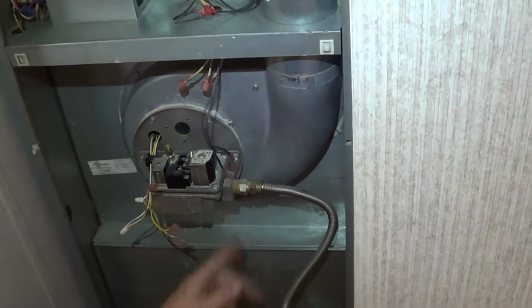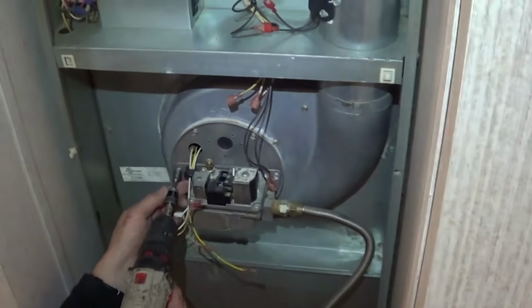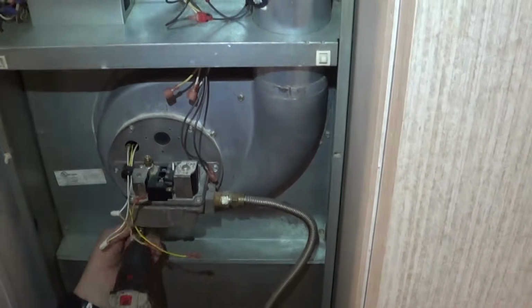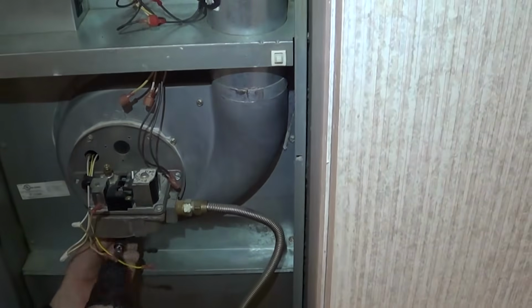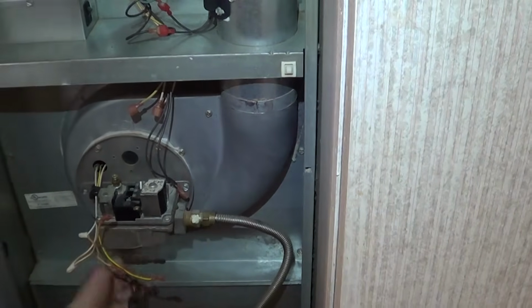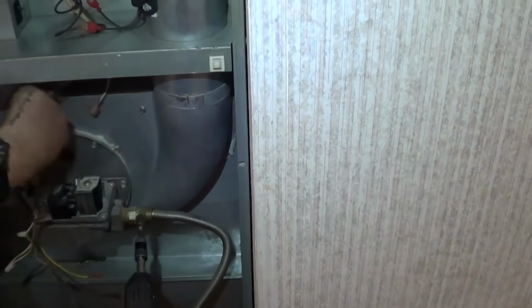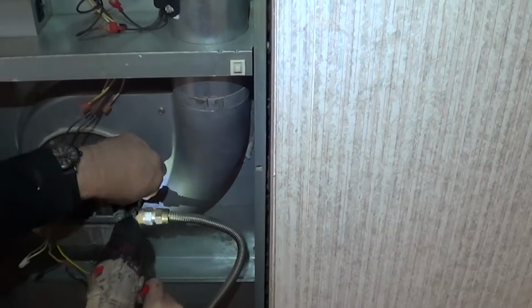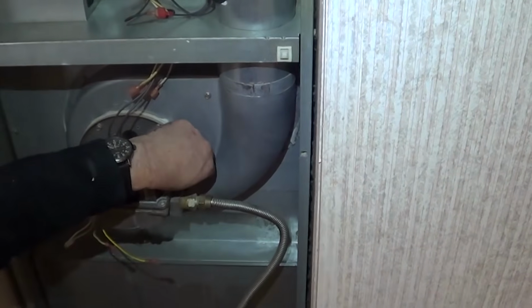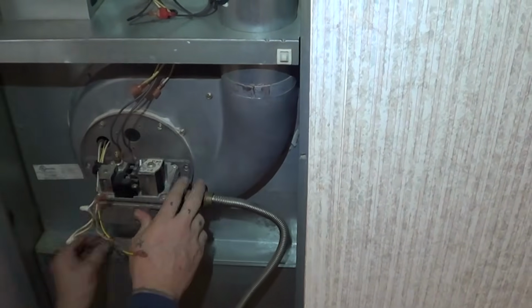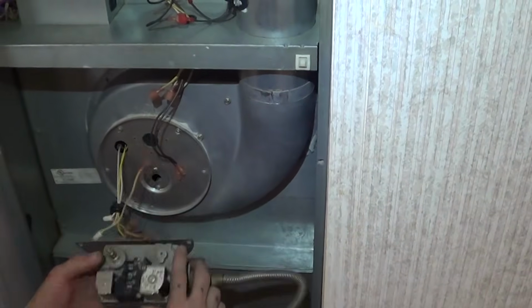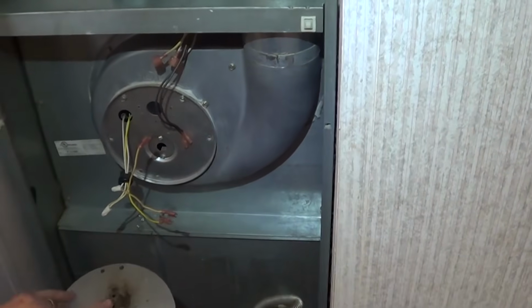We'll take those off to the side and remove all the screws for the gas valve here, again 5/16. If this one's on a flex line rather than hard piped in, this will work great, and it just comes straight out. If we turn it forward, we can see the orifice again.